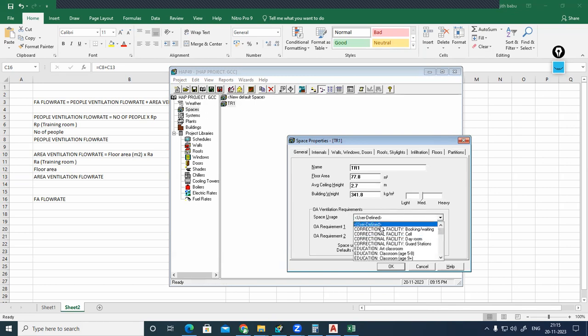Select the type of space. If training room is not there, no problem. You can select general conference room or meeting room. Scroll down. General conference or meeting. See, now you can see both the values are zero. When you select general conference or meeting, you can see the people ventilation, liter per second per meter square, is 0.3. Liter per second per person is 2.5. But it is not editable. You can't edit it, because the software is selecting this data from the ASHRAE standard only. Clear? So this will be easy for you.